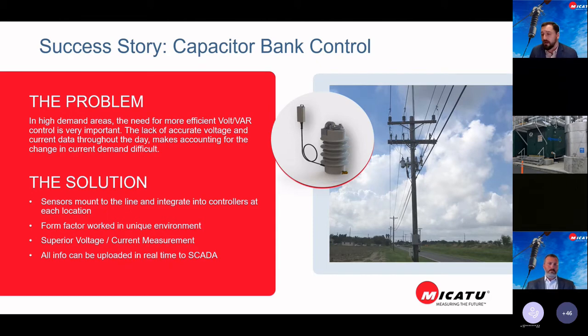A lot of customers are putting out cap bank controllers, and being able to have very reliable, accurate sensing to control that or send information back to the controller is really important. We've deployed our sensors - this particular example is a line post sensor, and we also have a line hanging sensor. Essentially, they're both doing the same thing: a combination voltage and current sensor used in different applications.